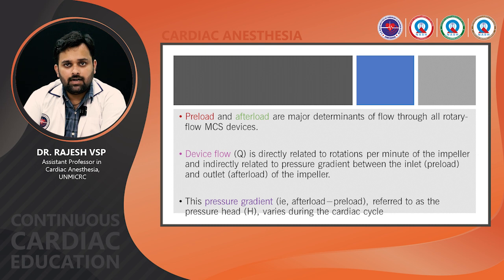Preload and afterload are major determinants of flow through rotary flow mechanical circulatory support devices. Device flow, denoted as Q, is directly related to rotations per minute of the impeller and inversely related to the pressure gradient between the inlet, that is preload, and the outlet, that is afterload, of the impeller. The pressure gradient, that is the difference between the afterload and preload, is referred to as pressure head, denoted as H, and varies during the cardiac cycle.